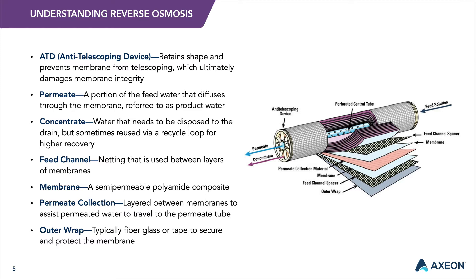In operation, the feed water enters the face of the element through the feed spacer channels and exits on the opposite end as concentrate. A part of the feed water, typically 10 to 20 percent, permeates through the membrane into the leaves and exits the permeate water tube. When elements are used for high permeate production rates, the pressure drop of the permeate flow inside the leaves reduces the efficiency of the element. Element construction is relevant because it also optimizes the actual active membrane area, the area inside the glue lines, and the thickness of the feed spacer. Element productivity is enhanced by high active area, while a thick feed spacer reduces fouling and increases cleaning success.